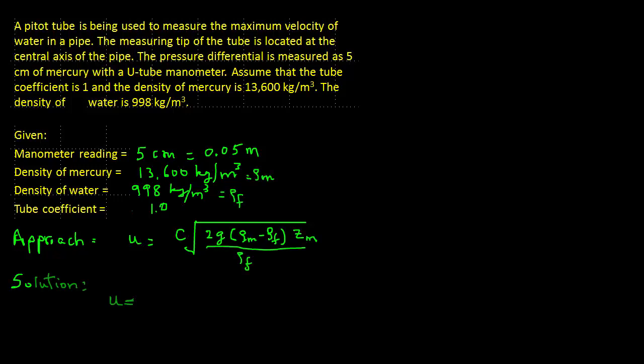We will substitute the various values in this equation. U will equal 1.0, which is the tube coefficient. Then we have in parenthesis 2 times 9.81 for acceleration due to gravity in meters per second squared. Density for the manometer fluid, mercury, is 13,600.